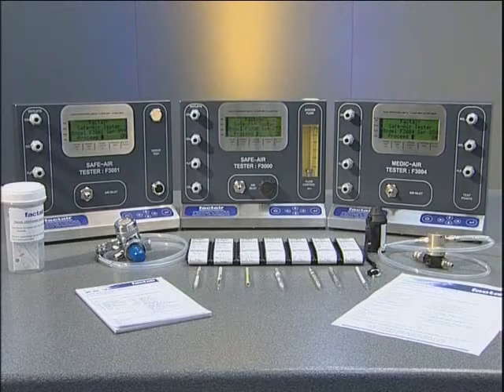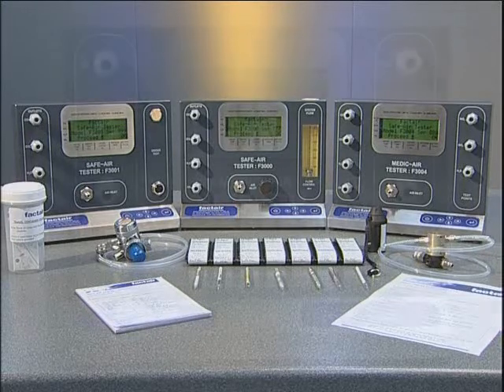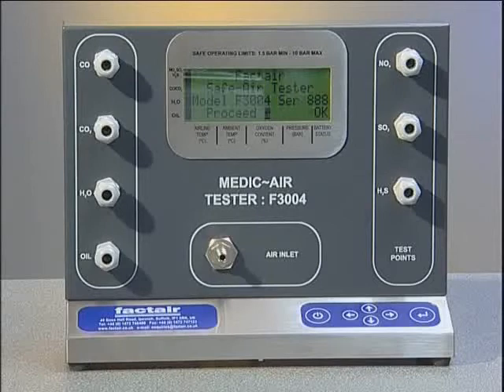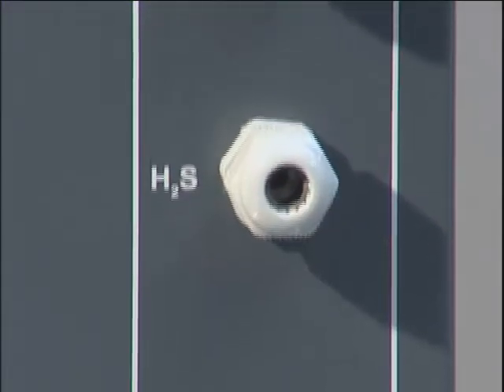Safe air testers are designed to provide a quick and easy method to carry out accurate periodic testing of breathing air supplies. The F3004 Medic-Air tester is designed to provide a quick and easy method of establishing the quality of medicinal air, as generally used in surgical, medical and dental applications. This is to the limits specified by European Pharmacopoeia and previously in the United Kingdom, HTM 2022. In this example, we'll be testing a typical medicinal air system.